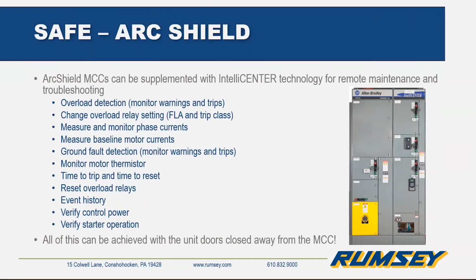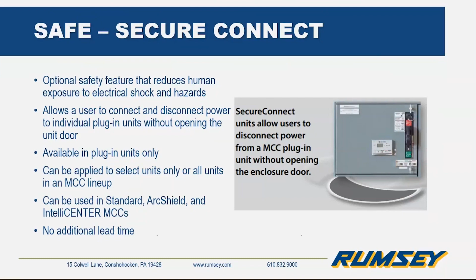So our next safety feature is SecureConnect. SecureConnect is also optional, and it's provided in plug-in units only. It's basically a design feature that allows somebody to disconnect power to an individual plug-in unit without opening the unit door. And I'll show exactly how that works on the next slide. But SecureConnect units can be inserted into standard ArcShield and IntelliCENTER MCCs. And not all the units have to be SecureConnect. Like, you can have a single SecureConnect bucket if you wanted to. It is important to note that SecureConnect buckets aren't guaranteed to fit into every MCC. Sometimes if the MCC is older, we would have to look at the compatibility much closer. But newer MCCs within the past few years, and obviously a new build, would be no problem.